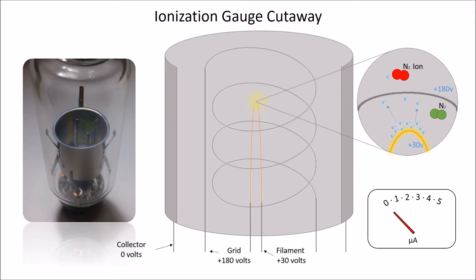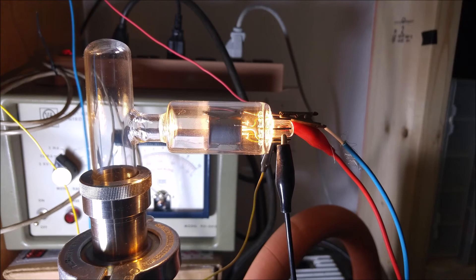This ion will then be attracted to the collector, where it will cause a small amount of current to flow. This current is directly proportional to pressure. Because of the ions present, the gauge will actually glow at low pressures.